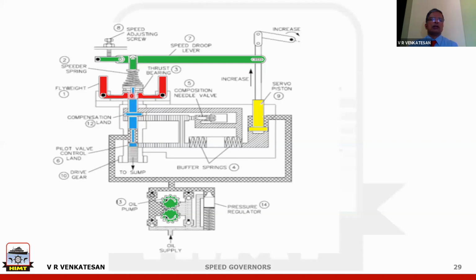So what this means is, as the pilot valve goes down, hydraulic oil moves towards moving the power piston. But the same hydraulic oil will also act on this part, and because it is acting on this part, it will move the pilot valve up again. So the normal working principle is, if the pilot valve goes down because of a drop in speed, when should it come back? When should it start moving up? Only when the engine speed increases. Only then should the pilot valve move up.